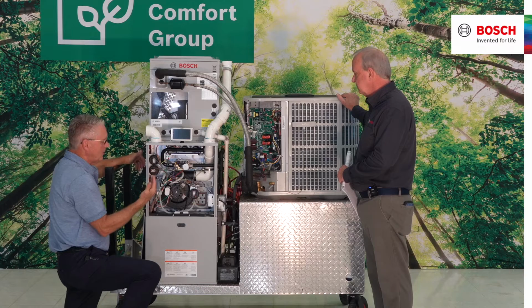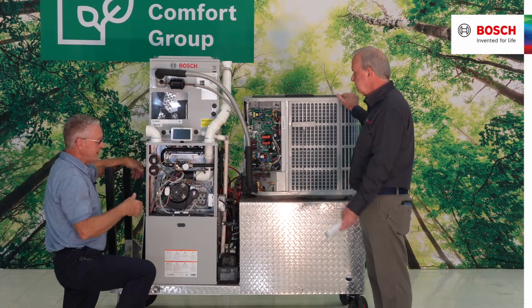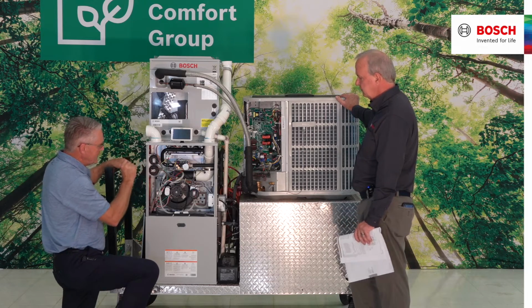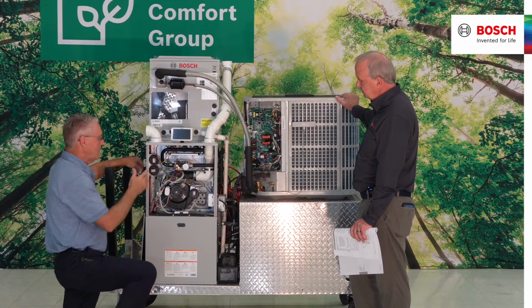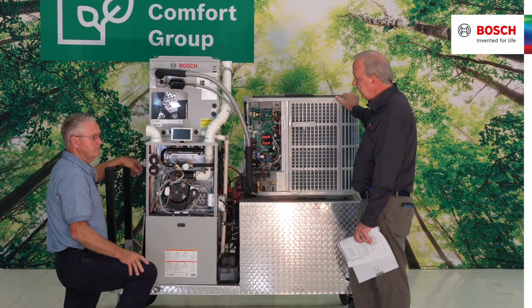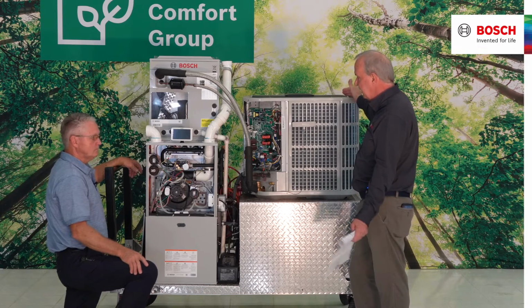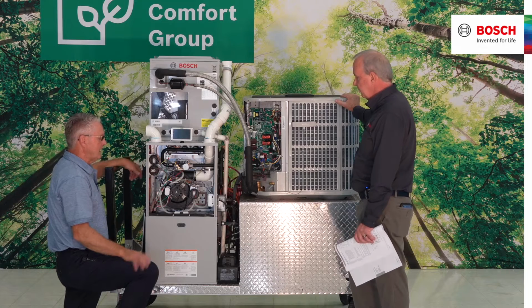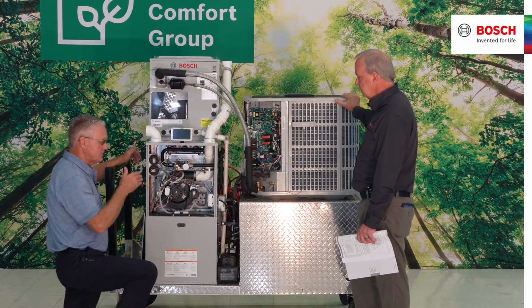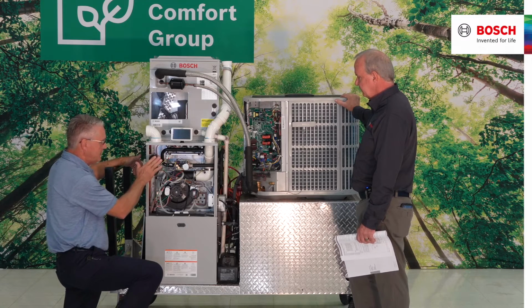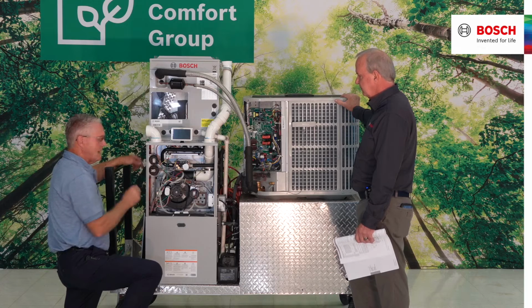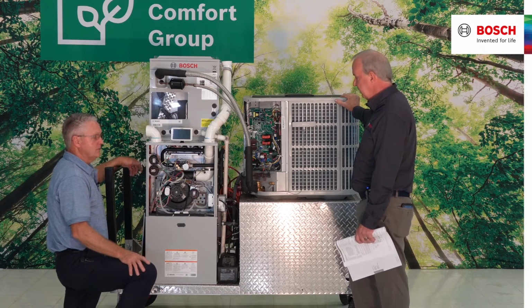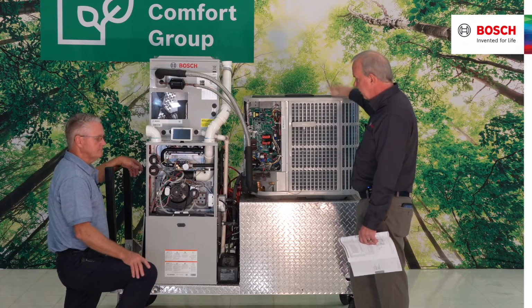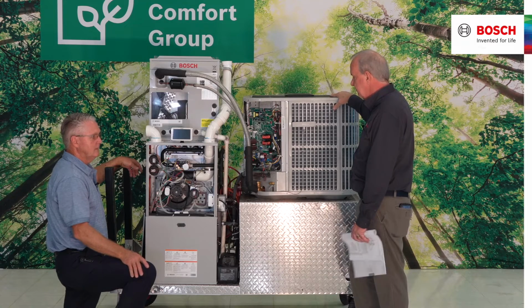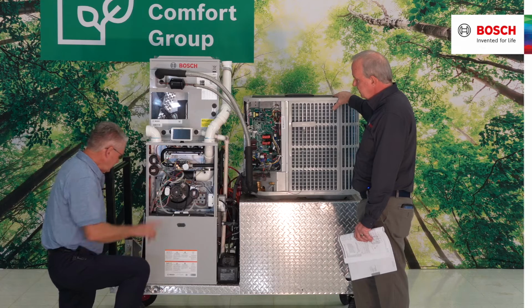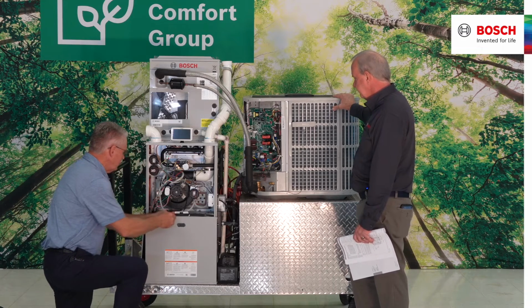It'll light up and the lights will come on and the fan will work in the summertime if you have reverse polarity, but when you turn it on for heat, the burners will not come on unless you get the polarity correct. So black being your hot, L1, or line one, and white being your neutral. Absolutely. And the next thing we need to talk about in that box is that, since I am a flame-proving rectification style system, I have to have a good ground. The flame sensor reports to the ground, and reports back to the motherboard to tell that we have flame, so that we can keep the gas on. Yep, absolutely.